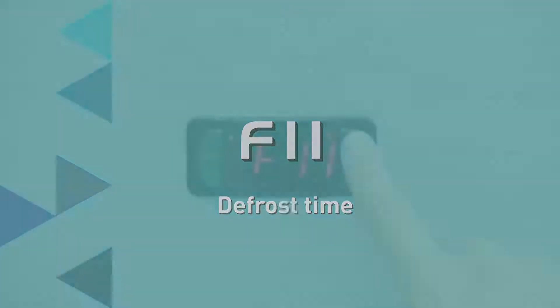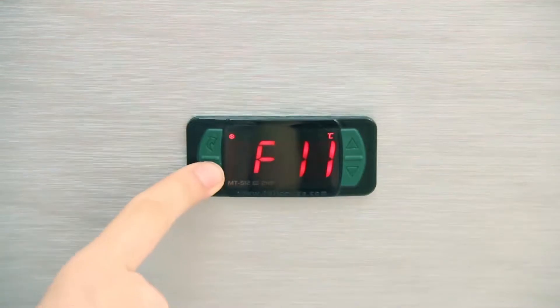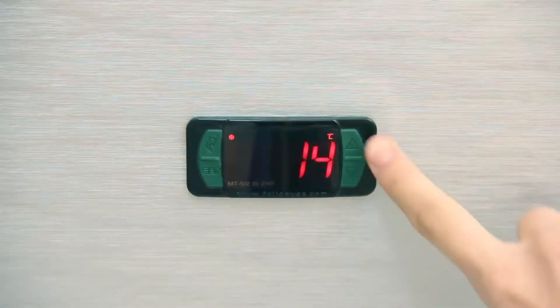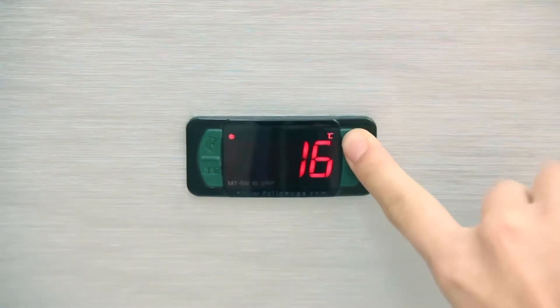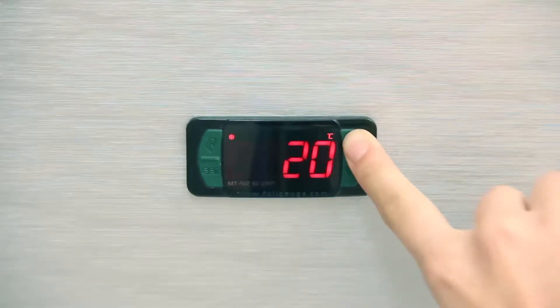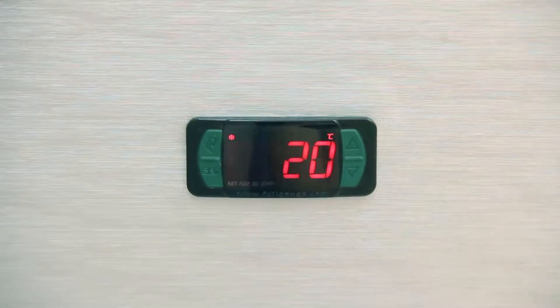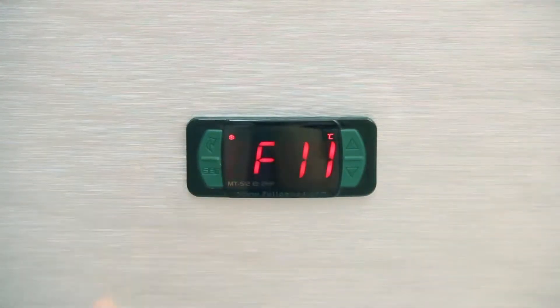F11 Defrost Time: It determines the minimum duration of the defrost time, that is, the time between cooling cycles. Select No so as not to adopt a minimum time, or provide a value between 1 and 999 minutes. In this example, we determined a time of 20 minutes.